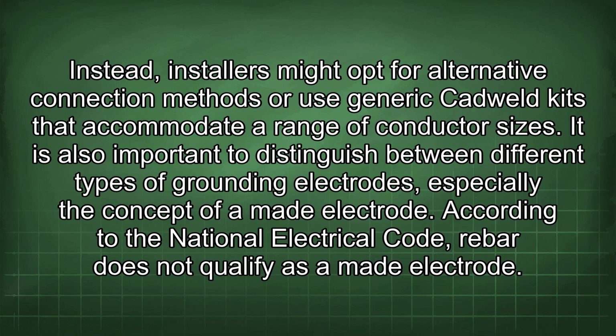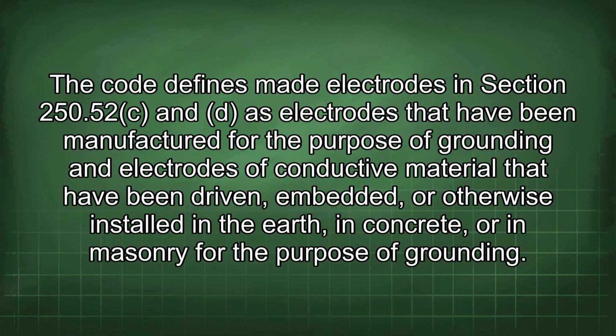It is also important to distinguish between different types of grounding electrodes, especially the concept of a made electrode. According to the National Electrical Code, rebar does not qualify as a made electrode. The code defines made electrodes in section 250.52 C and D as electrodes that have been manufactured for the purpose of grounding and electrodes of conductive material that have been driven, embedded, or otherwise installed in the earth, in concrete, or in masonry for the purpose of grounding.